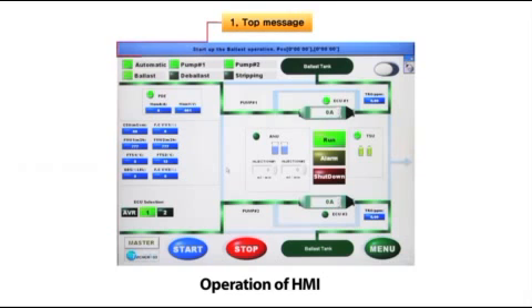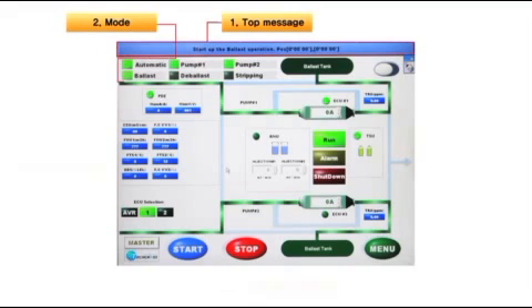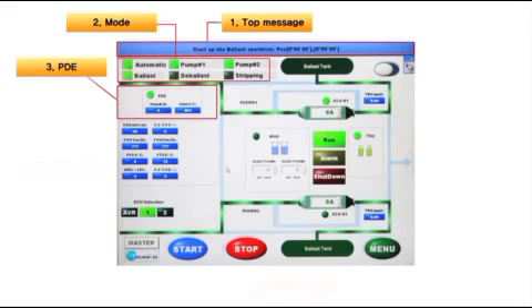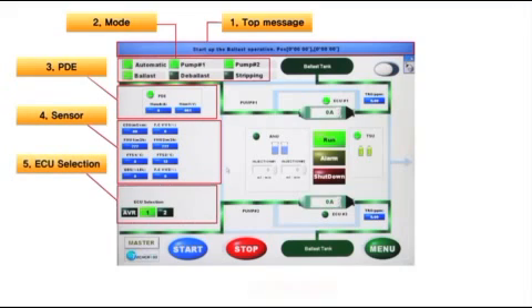2. HMI overview. 1. Top message: normal operation, alarm, fault message. 2. Mode: ECS operation mode: automatic, manual, ballasting, deballasting, stripping. 3. PDE: input voltages and electric current. 4. Sensor: measured values of ECS sensors, CSU, FMU, GDS, etc. 5. ECU selection: selection of ECU when there are more than 2 sets of ECU installed.